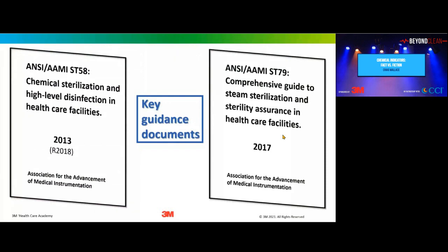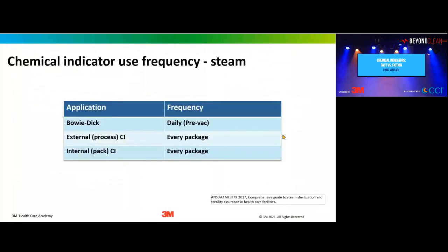So if we go into steam, we're going to just focus on chemical indicators, and we're going to focus on load release. So, just look at steam for chemical indicators. The different applications, so you've got Bowie-Dick, and the frequency of that for the pre-vac sterilizers only is going to be daily. The external process indicators are intended to be on every single package that's sterilized. And obviously the most common type of external chemical indicator is going to be indicator tape, but there's lots of other versions too, pre-printed dots or dots that are applied. Basically, they've got to be on the outside and make it easy to see if the package had been processed or not.